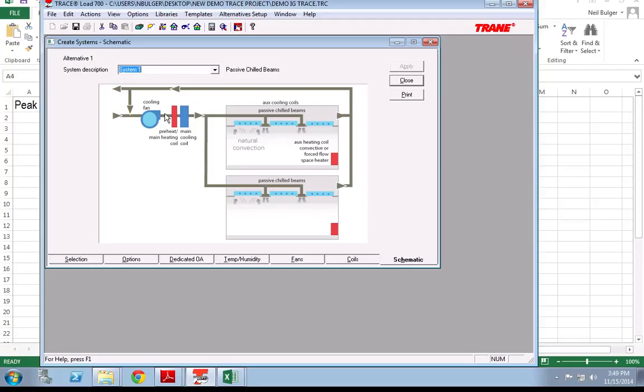If you did it that way, your coil would likely be undersized, maybe by 20 to 30%, enough that it's noticeable. So that calculation can be done in a few ways. How to actually break this problem out could be done in Trace if you are aware of how to use Trace in a little more advanced way. And that's what I want to talk about.